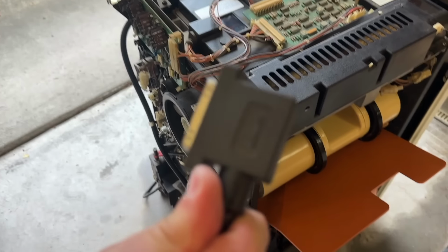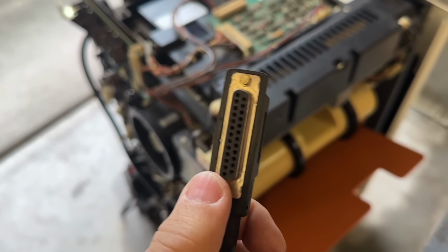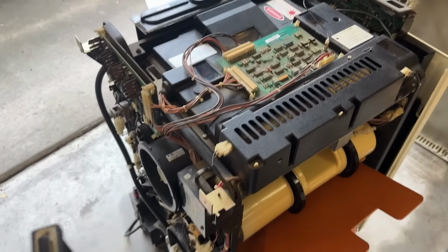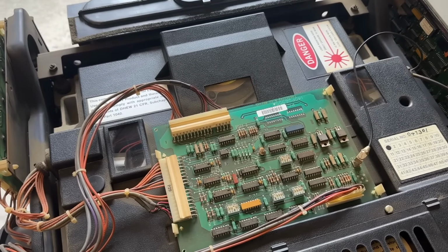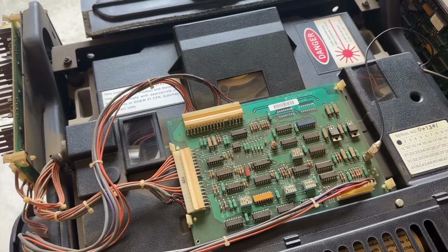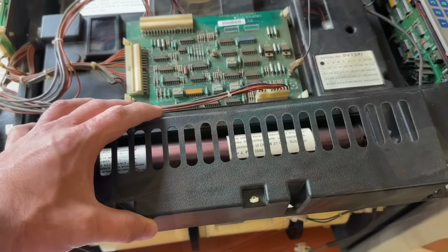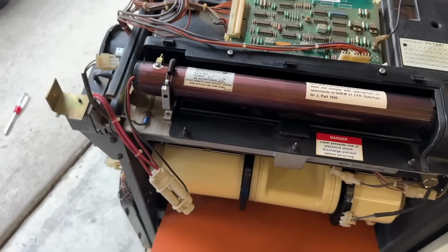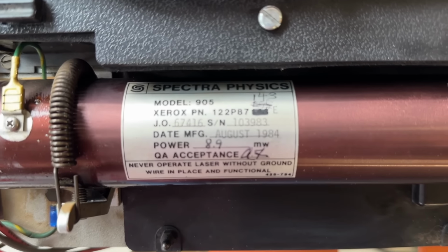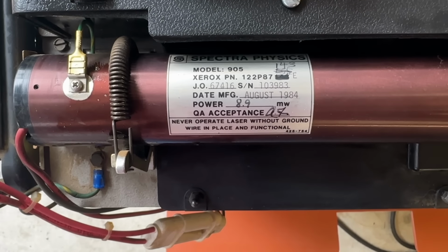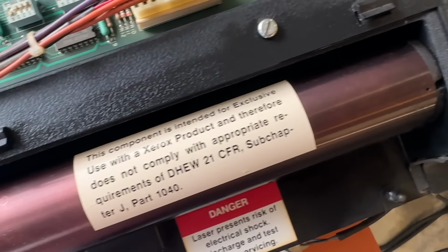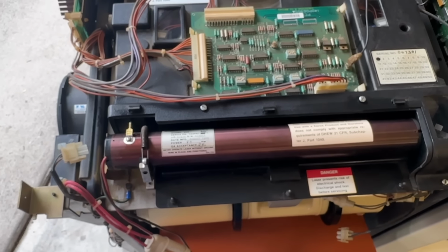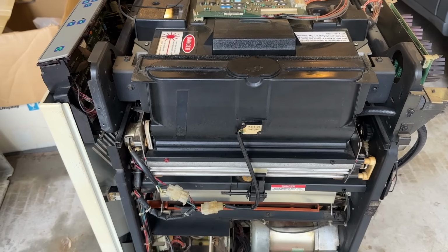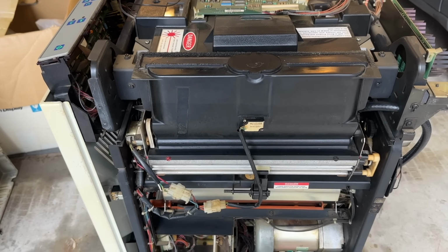The actual image data comes in over the cable going back to the 8000. It's getting horizontal sync pulses and vertical sync pulses from the printer, and then the computer directly controls the laser. After removing this cover and interlock, let's take a look at this laser. That is not something you would see in later devices. Service isn't necessarily as bad as you might think.